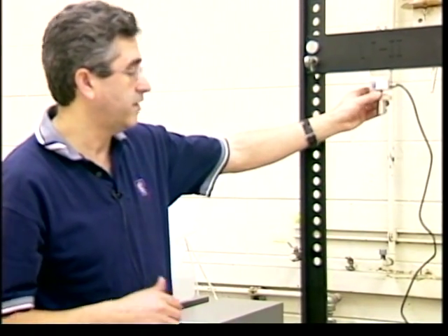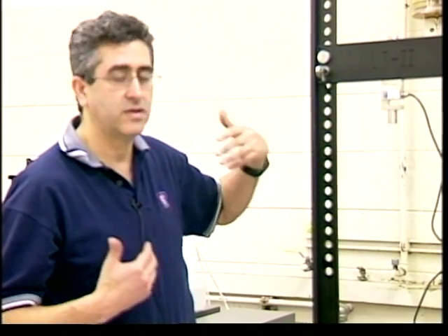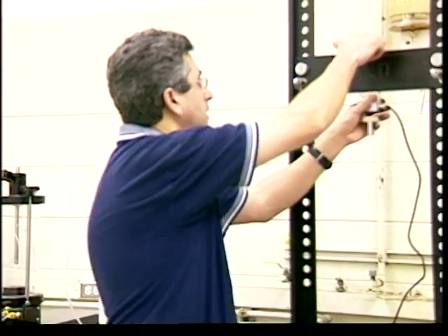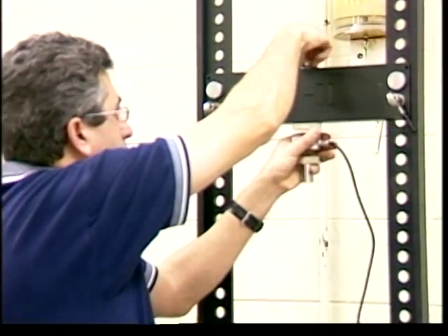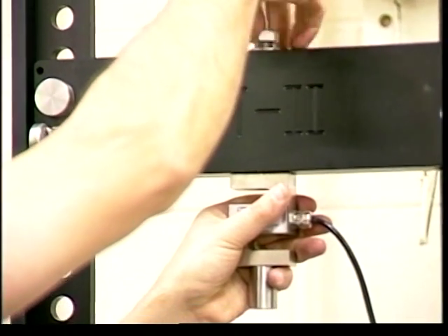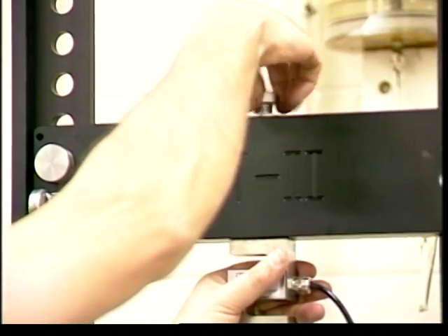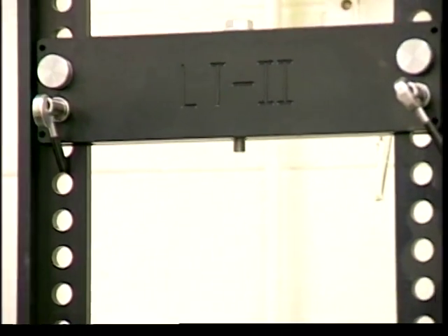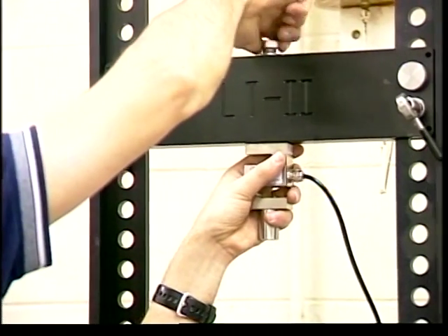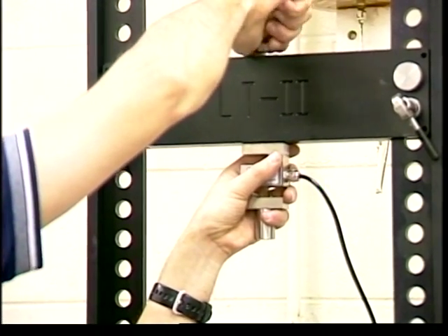Now, if you have a different load cell that you're going to be using with a different capacity, like a 5,000 pound or 250 pound load cell, all you have to do is unscrew it from here, and then put your new load cell in and connect it in the back. The only thing you have to be very careful about is that if you change the load cell, the calibration factor of the load cell has to change. So I'm going to put my load cell back in here, and this is the one that we're going to be using for this test.